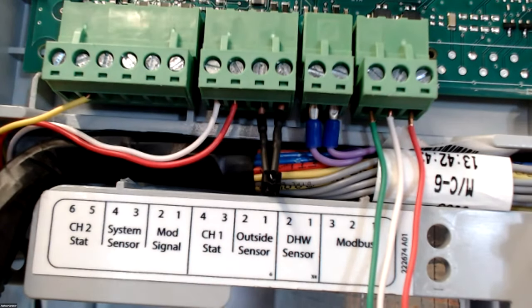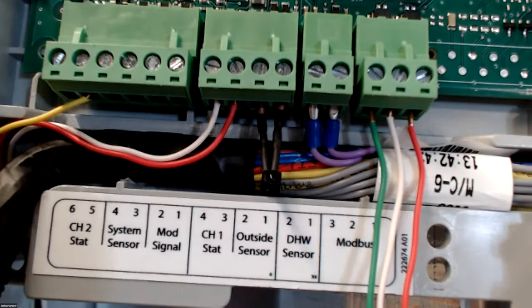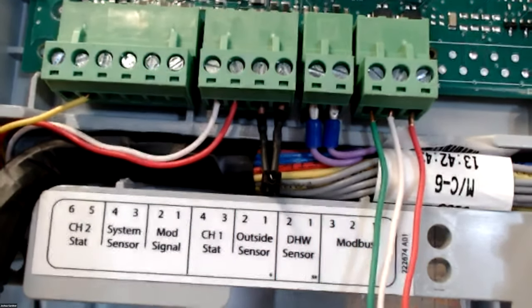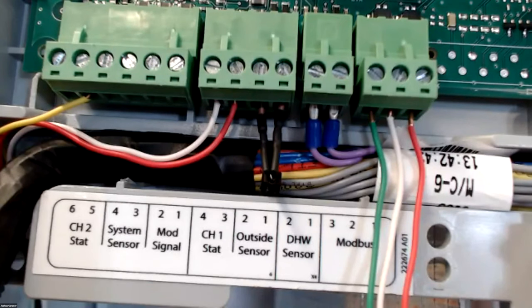And I've seen a lot of guys, most guys, just strap it on with zip ties. Occasionally I see some systems overshoot. So my recommendation is, if you're doing cascading or using your system sensor, I highly recommend using an immersion well and getting it into the stream of water. If you do that, you get a much more accurate temperature and it pretty much prevents overshooting with that unit. There are ways we can go into the control and slow the unit down and prevent overshooting. But if you can get an immersion well and a tee into the outlet side on that, it will prevent that from happening in pretty much all the installations that we've had.